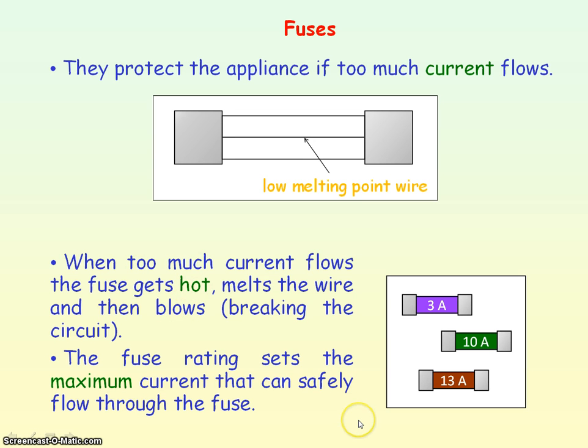If you have an appliance whose normal operating current is, say, 2.5 amps, the best fuse to use is 3 amps, just above the normal operating current.